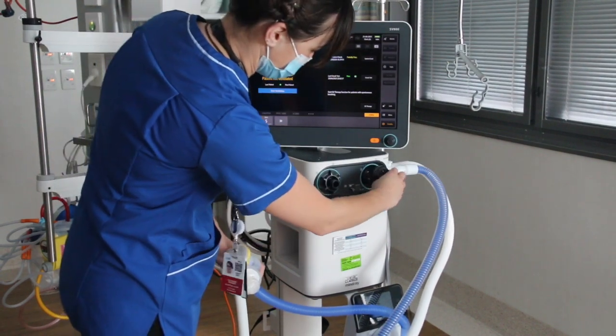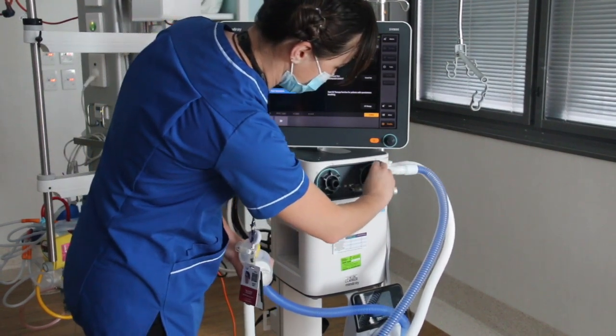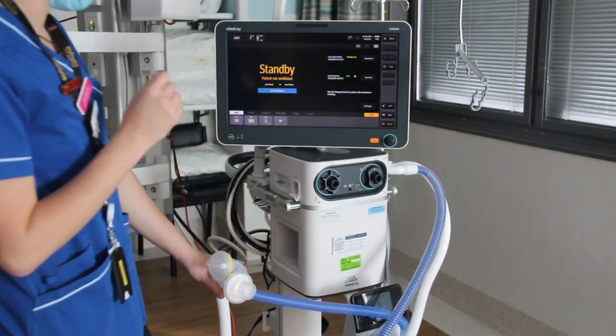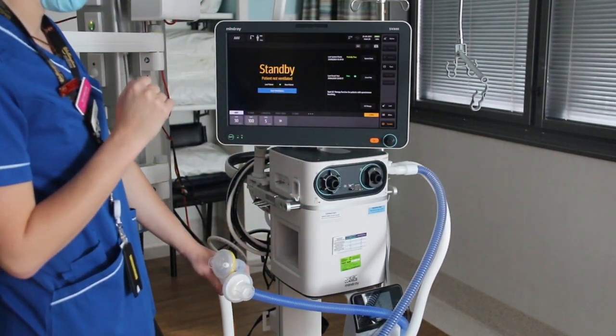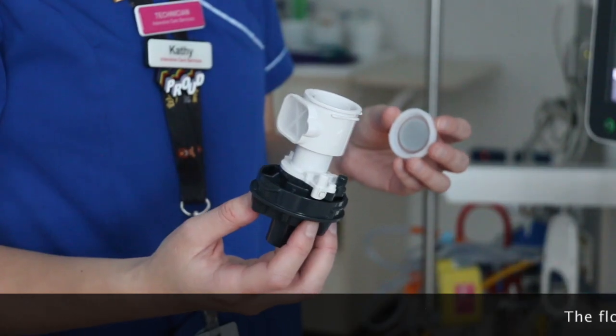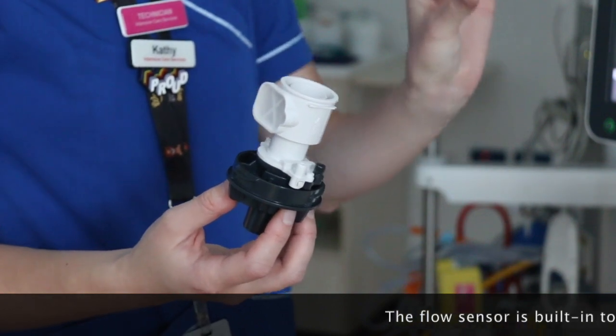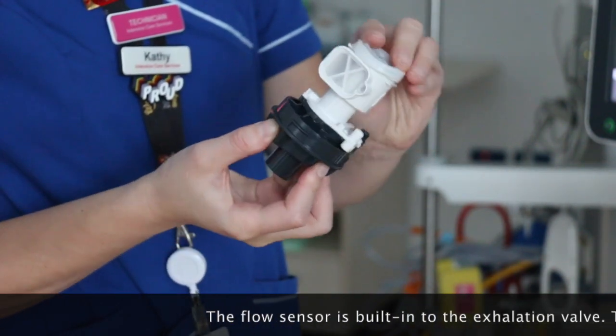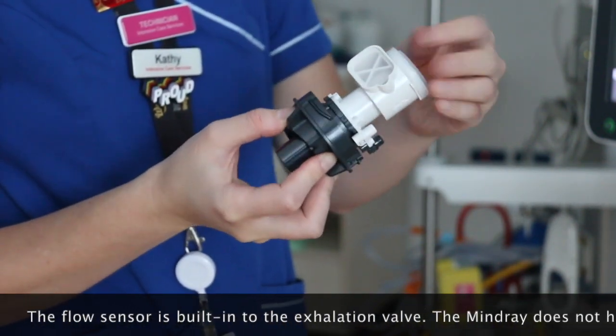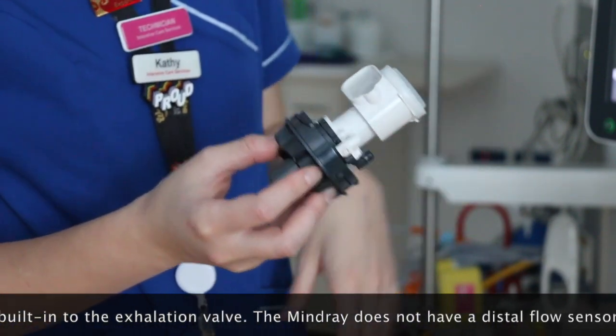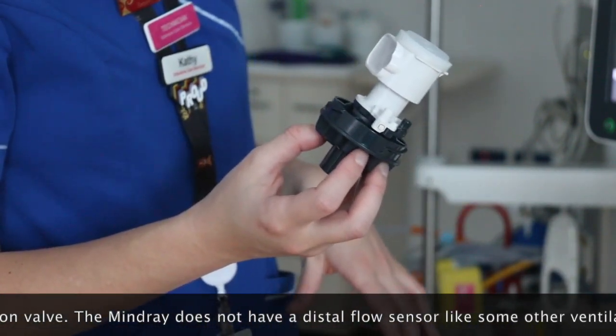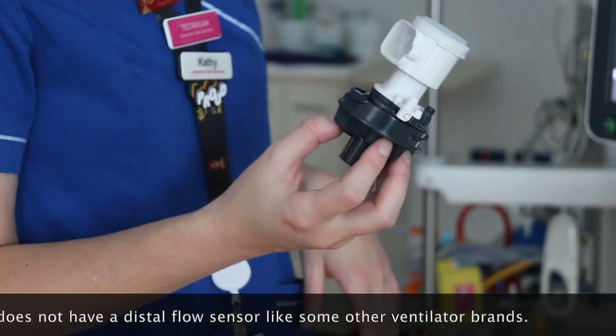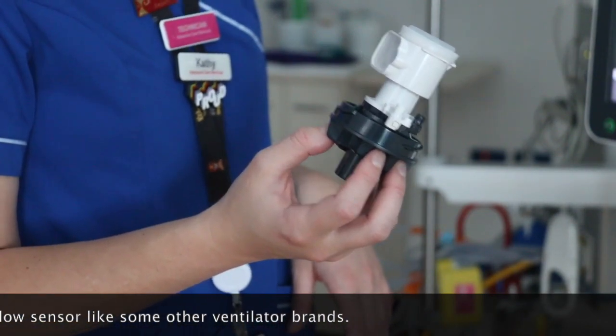That might be a piece of kit that isn't in your current ventilators but is in the Mindray. We just leave that in there constantly. It gets changed on annual servicing, gets it clean. This is your exhalation valve. You want the diaphragm to be covering this bit here. We send this for sterilising in between every patient, and the most important part of the checks that we've found is calibrating your flow sensor to your ventilator before you do your system check.